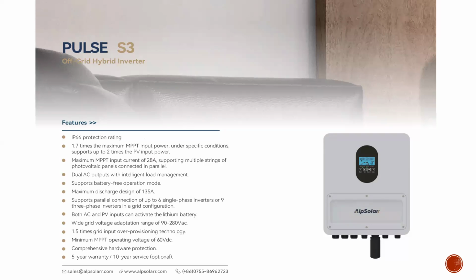And then the next unique selling point about this system is the fact that it is scalable. It allows parallel operation of up to 6 units when you are connecting as a single phase system. And if you are arranging them in 3 phases, it can take up to 9 units of the inverter. So it gives your client that wants to grow small the opportunity to start small, right? So let's say it's a client that wants an 18 kilowatt system but does not have the financial capacity to start up with an 18 kilowatt system. It can start with just 6, and over time it can scale to meet up with his inverter system.